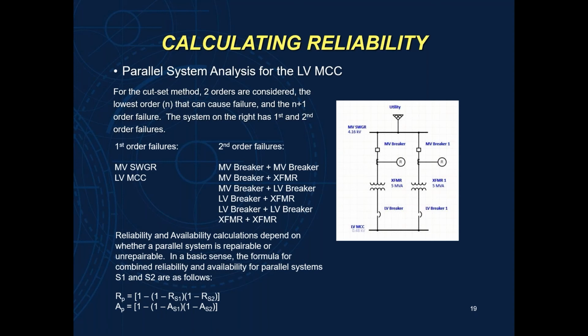We also have second order failures because we have two branches that are fully redundant. Okay, so we have 6 combinations that could occur and those 2 branches that could cause a failure. So this is how we determine what our failure modes are.